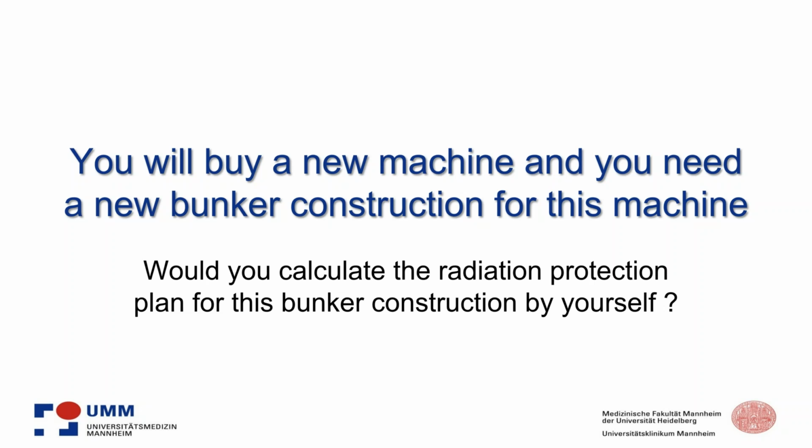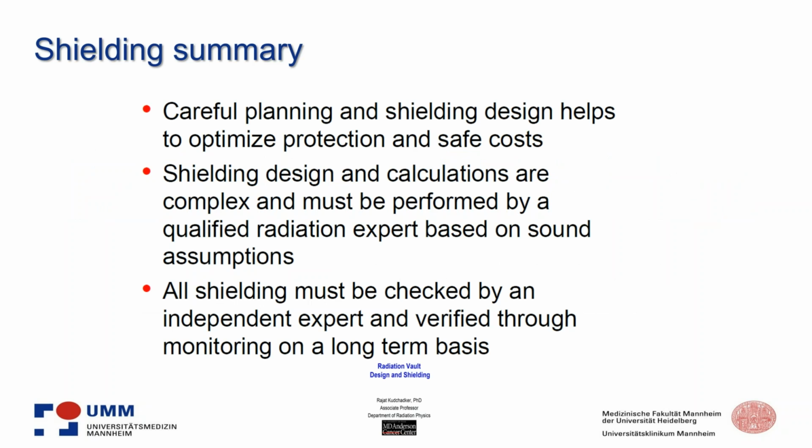And at the end, a bunker for a treatment machine is not a closed cube of concrete. This bunker has to be connected to the outside, so to the electricity. You need cabling, plumbing, and all these things have to come into the bunker. A linear accelerator is a complex machine, and this has to be connected inside the bunker. So you have to open the bunker at some point, and all these things have to be covered by the radiation protection calculation.